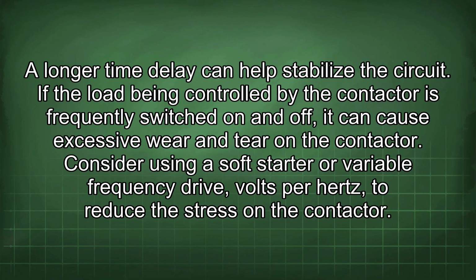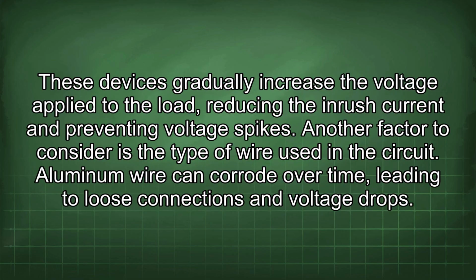If the load being controlled by the contactor is frequently switched on and off, it can cause excessive wear and tear on the contactor. Consider using a soft starter or variable frequency drive, volts per hertz, to reduce the stress on the contactor. These devices gradually increase the voltage applied to the load, reducing the inrush current and preventing voltage spikes. Another factor to consider is the type of wire used in the circuit.